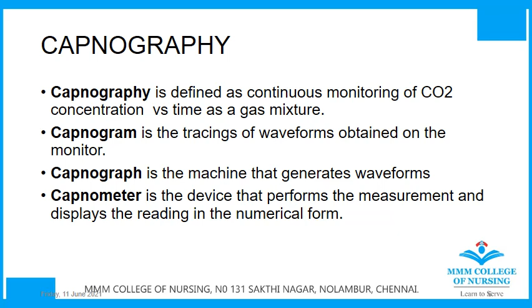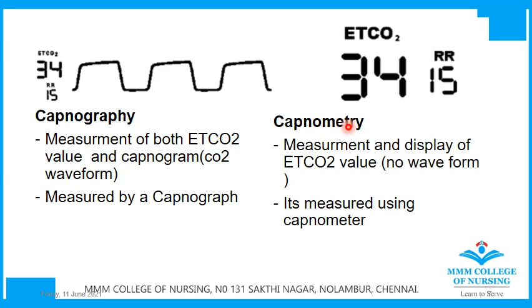This is capnography. It is the measurement of both the EtCO2 value and a capnogram, that is the carbon dioxide waveform, and the reading will be displayed on the monitor. So it is measured by a capnograph. This is the EtCO2 value which you can see here. This is a capnometry reading. So it is the measurement and display of the EtCO2 value with no waveform. Here you can see in capnography the waveform, whereas in capnometry you will not be seeing the waveform. So it is measured using a capnometer.